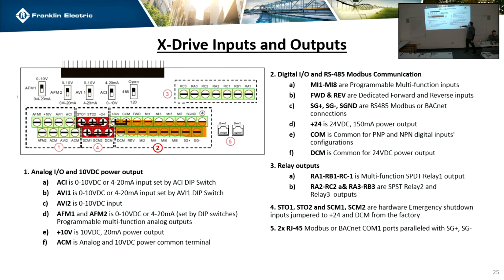There's also a 24 volt power. We do not wire this to terminals or anything. It's always going to be on the drive itself. And it's got a little jumper right here that goes to our COM. And we normally use the NPN setup so that all you need is digital inputs. And that's part of that setup, is leaving that jumper in there. So if you get a drive and you're putting jumpers somewhere and it's just not registering, one of the first things to look for is that jumper. People will pull it not knowing what it is.